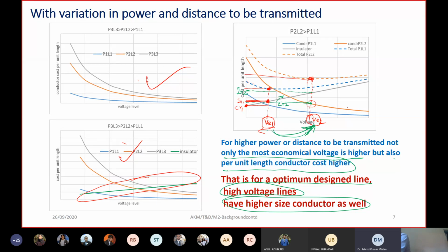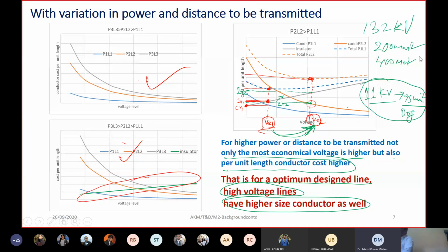The conductor size we usually choose for 11 kV is a 95 mm square conductor. The highest size conductor usually used for 11 kV is called the dog conductor - I don't know whether you know the names of conductors or not. This is the highest size conductor used for 11 kV. But for 132 kV or 220 kV, this may be the lowest size conductor. The higher size conductor may have a size of 200 mm square or 400 mm square. So what does this mean? As we go for higher and higher voltage lines, the conductor sizes are also higher. Don't confuse this - going for higher voltage does not mean the size of conductor is lower.